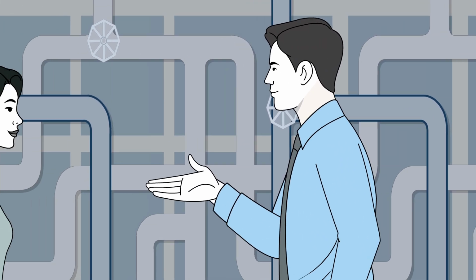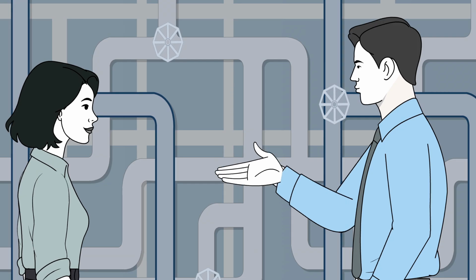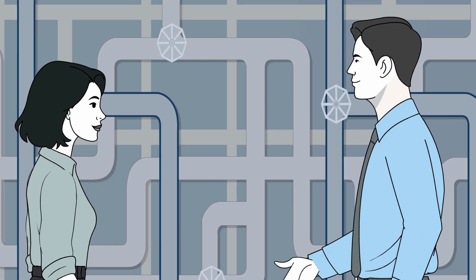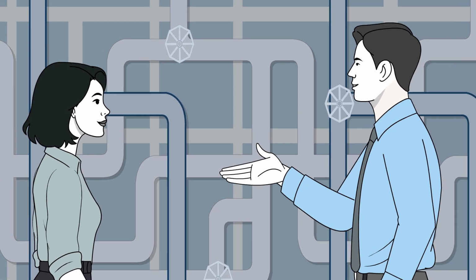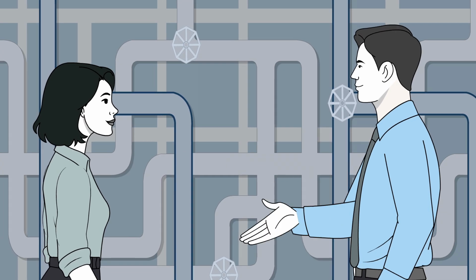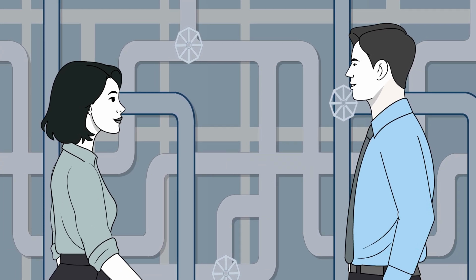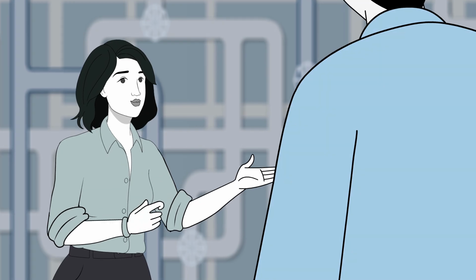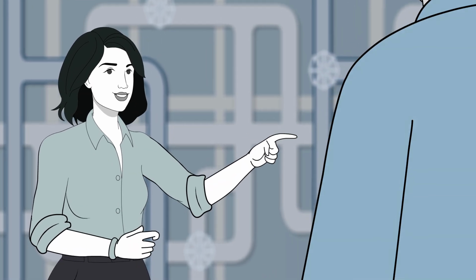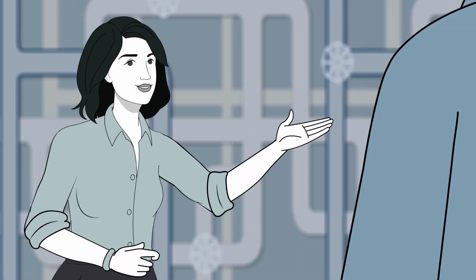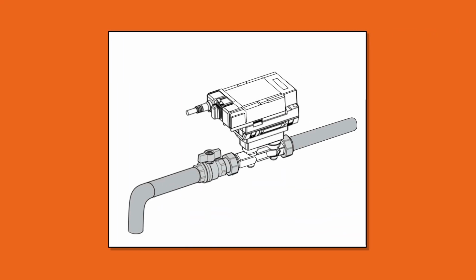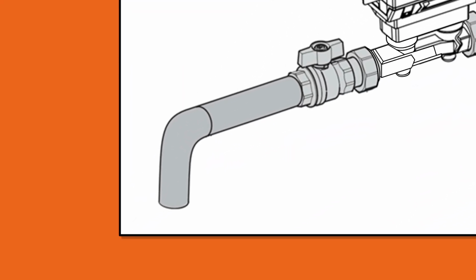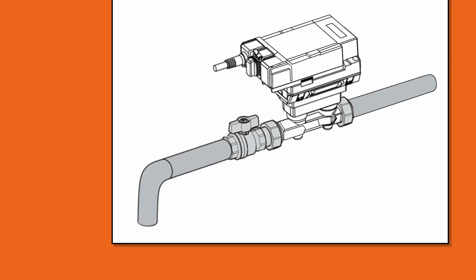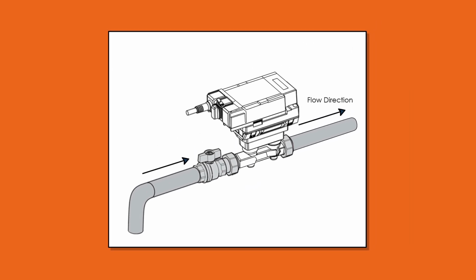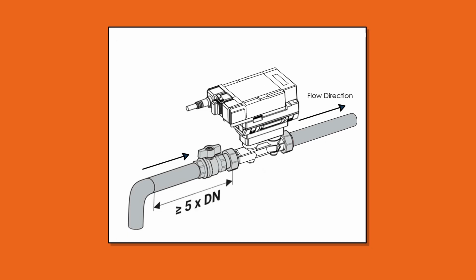Hi Anna, thanks for meeting me on site. We're in the process of installing and commissioning our thermal energy meters into the new section of the mall, and we were wondering whether there's anything we need to keep in mind. Hi Shane, thanks for organizing. When it comes to installation, there are some things to take into consideration. Belimo recommends having a straight section of pipe leading into the thermal energy meter so that the flow has time to settle. The length of the straight pipe should be at least 5 times the pipe diameter.